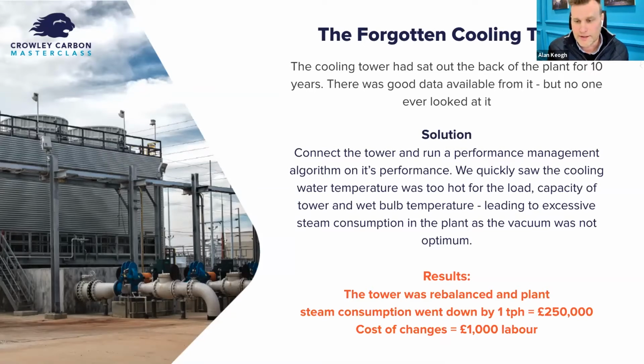When we connected it up and ran it through our performance algorithms, we saw that the water coming out of the cooling tower was too hot for the load on the cooling tower and for the ambient conditions on that particular day. The cooling water was being used to drive vacuum in the factory, so the colder, the better. The colder, the deeper the vacuum, the less steam consumption would be in the factory.